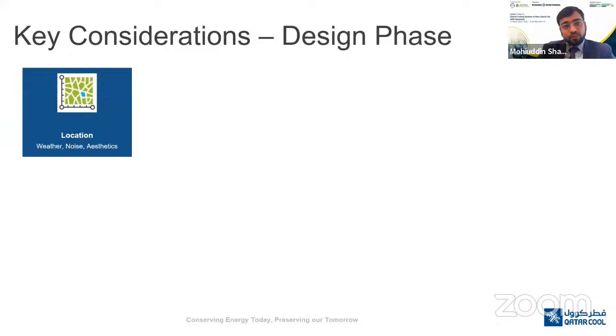The location of the plant is one of the key aspects, firstly in terms of the weather. The weather conditions have to be considered while designing the plant, especially since most district cooling plants are water cooled, so wet bulb conditions play a critical role. If the weather is dry, it has different challenges compared to where the weather has higher wet bulb conditions. Indonesia being an island nation, most of the developments would be on the seashore, so it would experience higher wet bulb conditions, and cooling tower sizing would especially get affected.